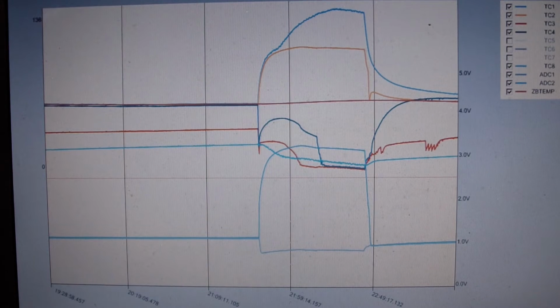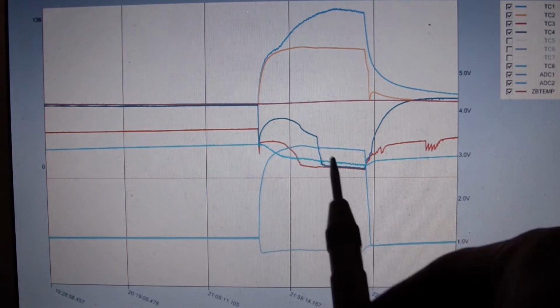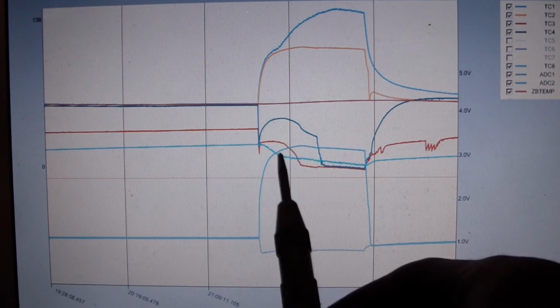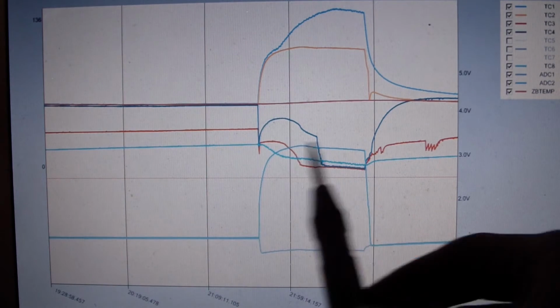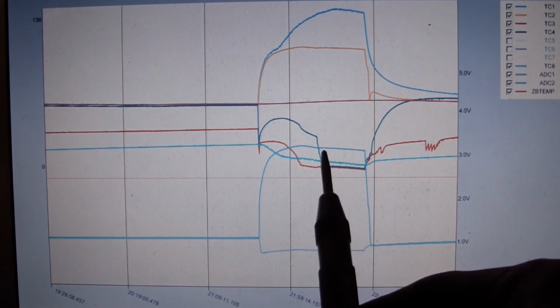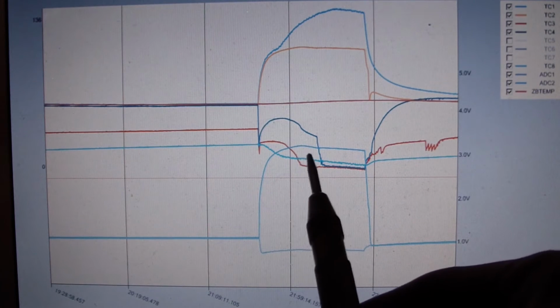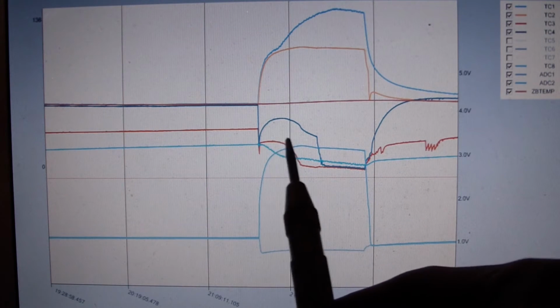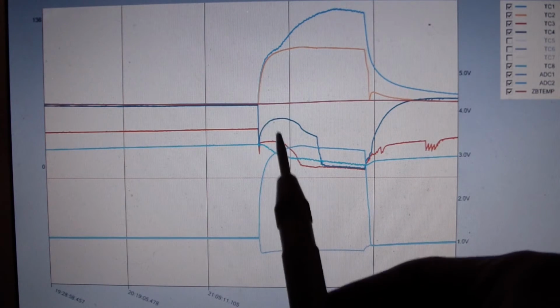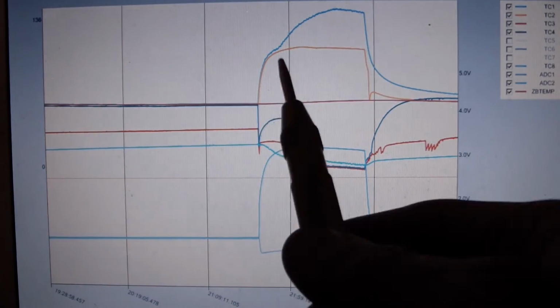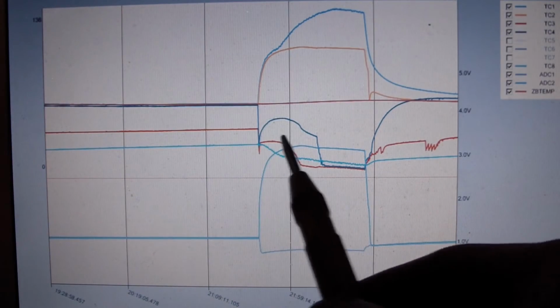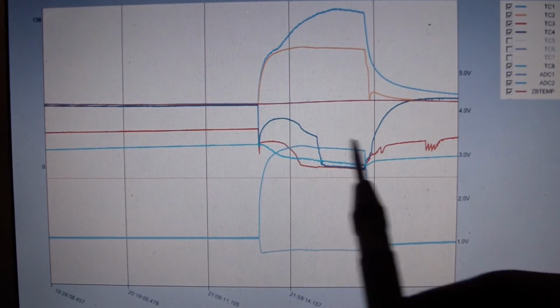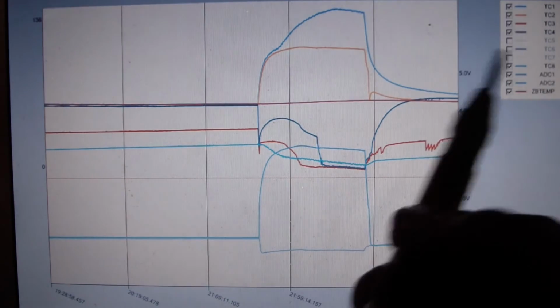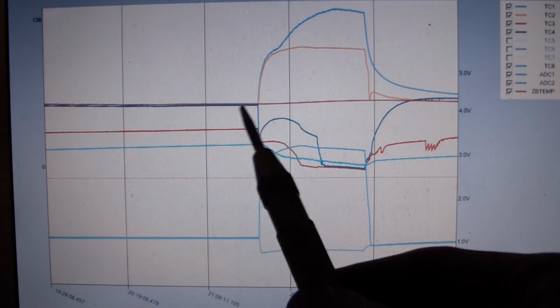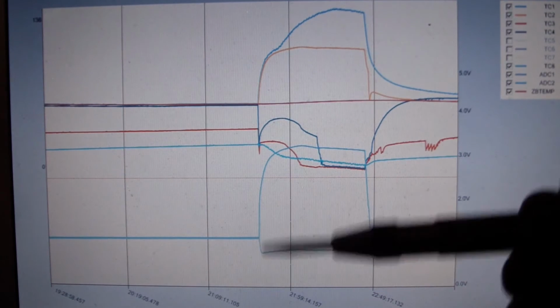So what I'd like to do is reduce this first half here. This we're getting actual real cooling that's occurring in there, but I'd like to get down as close to saturation as quickly as possible in the run, to gain that liquid plug rather rapidly. Something else I wanted to point out, and I forgot about this. This is pretty important. One of the things that changes during this run cycle, apart from everything, is the conditions that the evaporator is in.